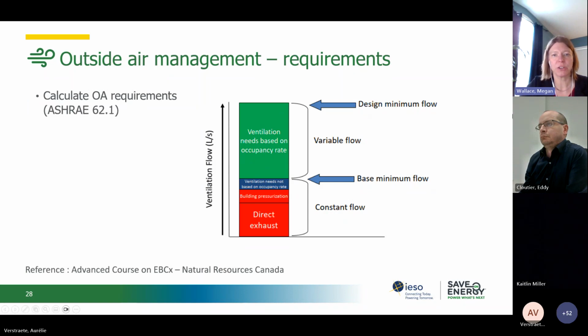So what we want to do is make sure that we have the correct amount of outdoor air for the building. We can calculate the outdoor air requirements using ASHRAE 62, which is the guideline specified by the Ontario Building Code. ASHRAE 62 says the building will have two separate outdoor air requirements. There's the constant flow, the air that has to go into the building, that's your base minimum. That'll be makeup for direct exhaust, for washroom exhaust, for example, or outdoor air you need for building pressurization.